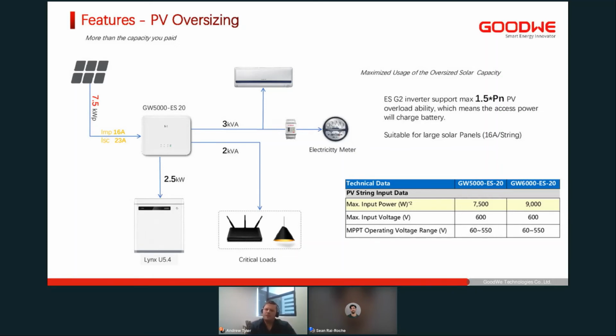And then on the bottom right, we've also got a table that shows you the 5 and 6 kilowatt next to each other. I just wanted to highlight the PV input power. So you'll note on the 6 kilowatt, we can go up to 9 kilowatts of PV. So in this example, you would run 6 kilowatts of AC power while still charging your batteries at 3 kilowatts. So really great feature, and something that is common amongst all of our hybrid inverters, for those of you who didn't know.